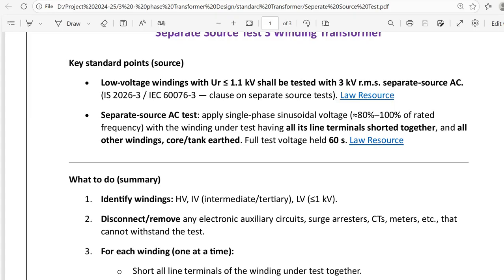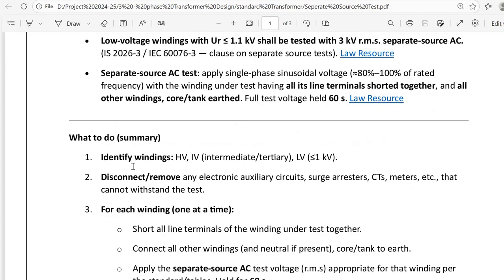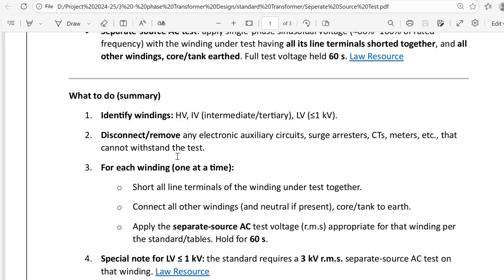So what to do as per the summary? Identify the windings. Which one is the HV winding? Which one is the LV winding? Then the intermediate and any tertiary winding. Generally, it is the LV winding and HV winding. Disconnect and remove any electronic auxiliary circuit, like surge arrestor, CT, meter, etc., that cannot withstand the test.